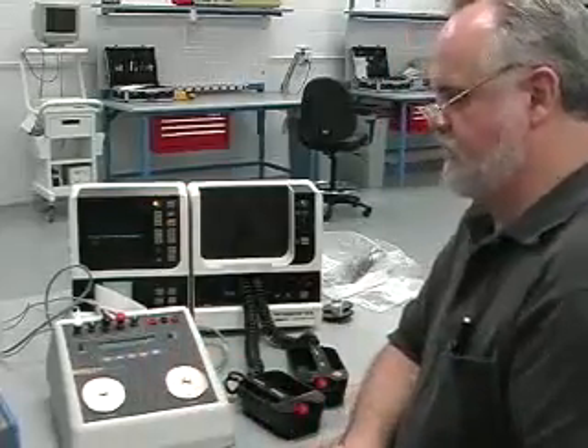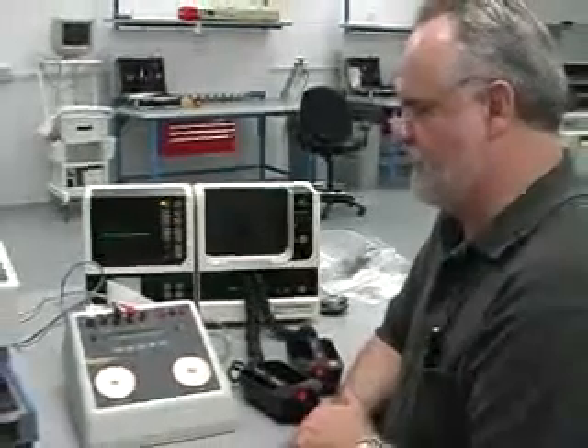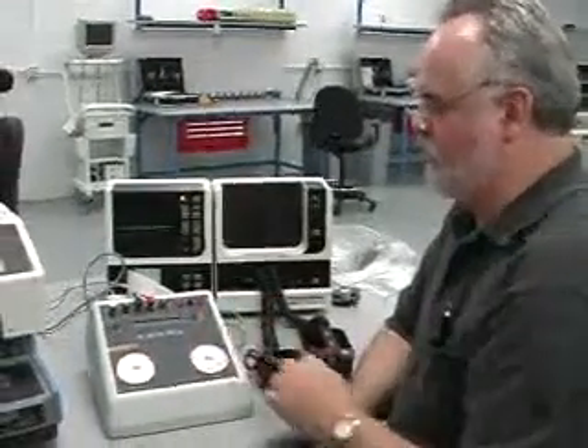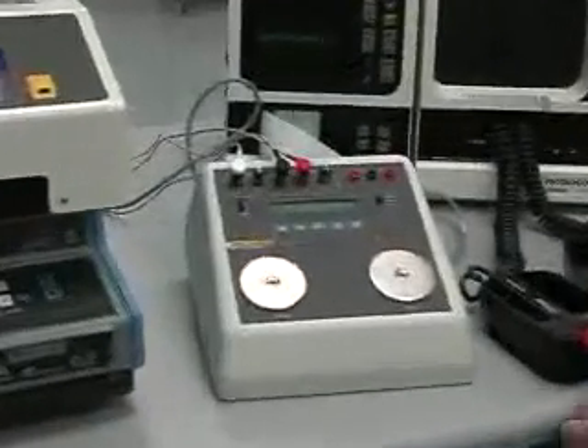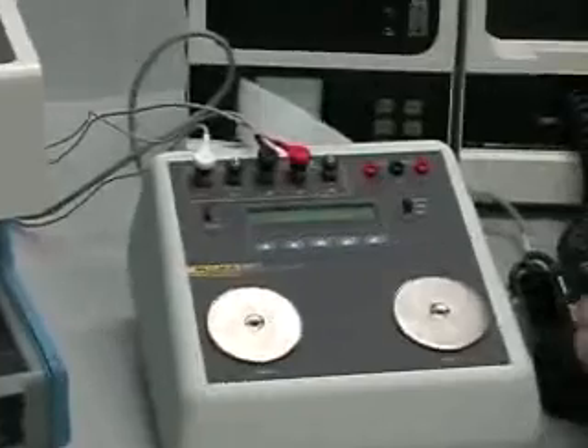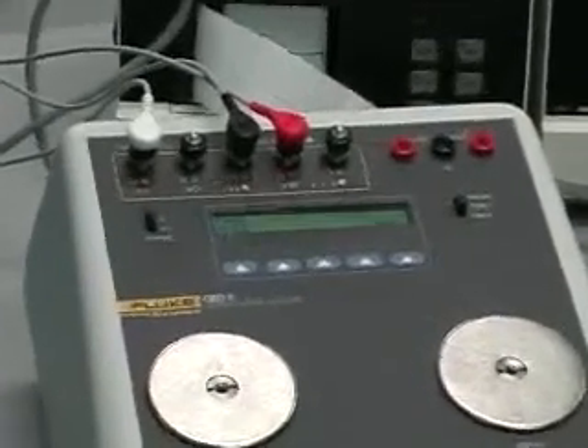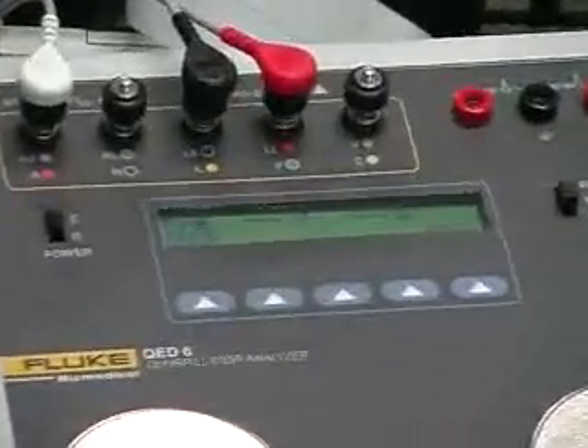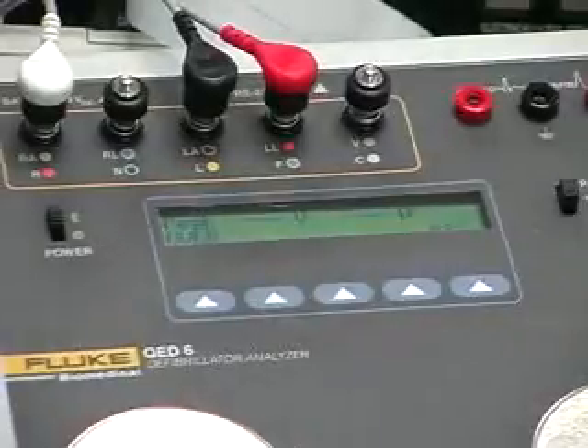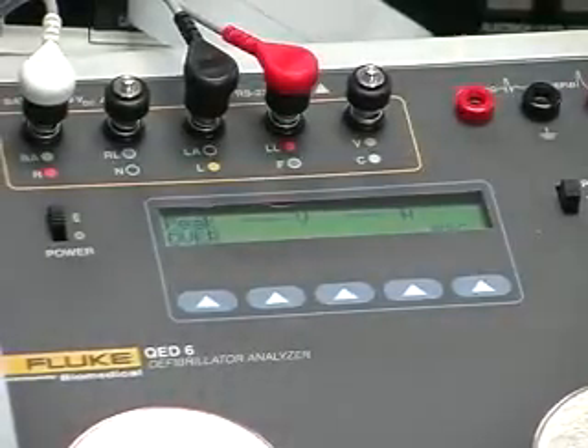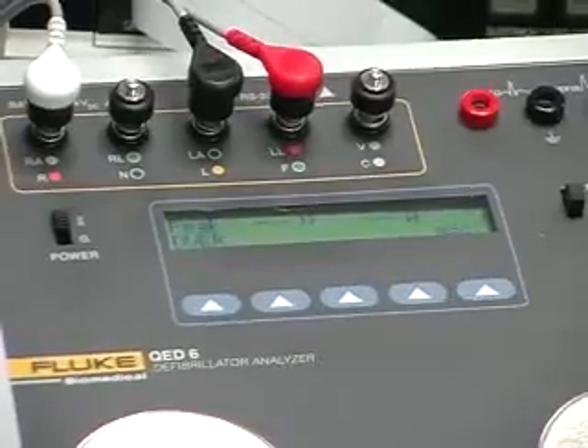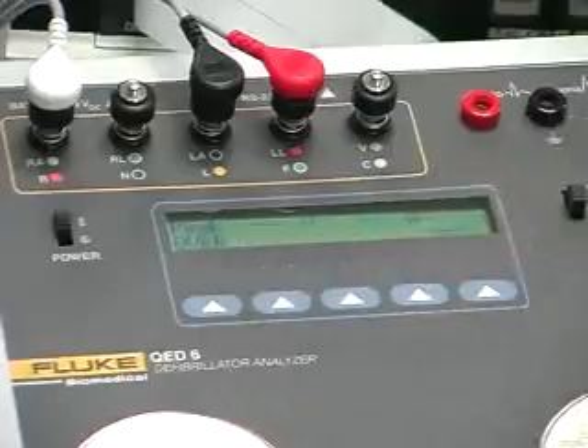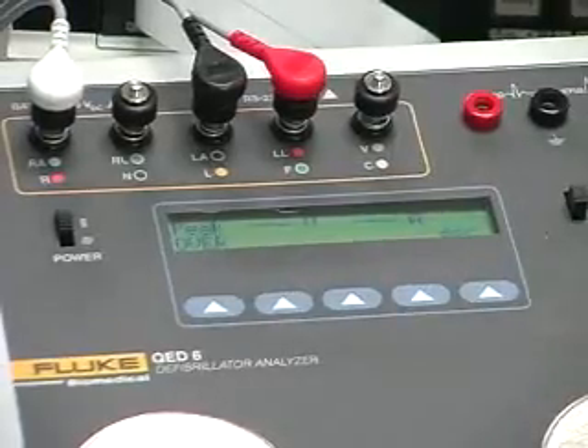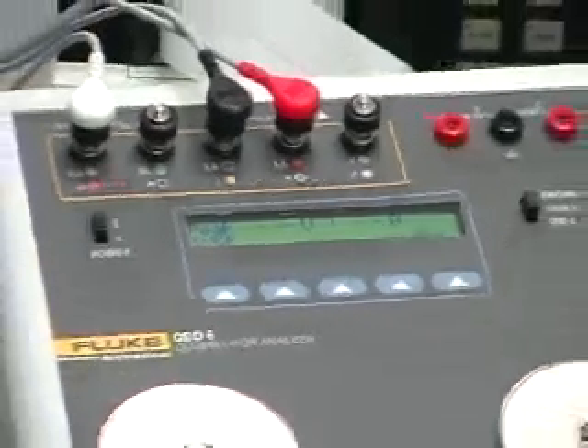Okay, a couple of other tests that you can do for the defibrillator. Escape up to the main menu 1, and you can go in and measure peak voltage and peak amperage. Remember, this is a very high energy device, so you are going to be looking at very high levels of voltage and current. This measures the initial peak and gives you that energy value, and then we have the over, which will simply give you any energy or any voltage or current within the second lobe of the discharge. Remember before, when we had that playback waveform, there was a little bit of a negative.